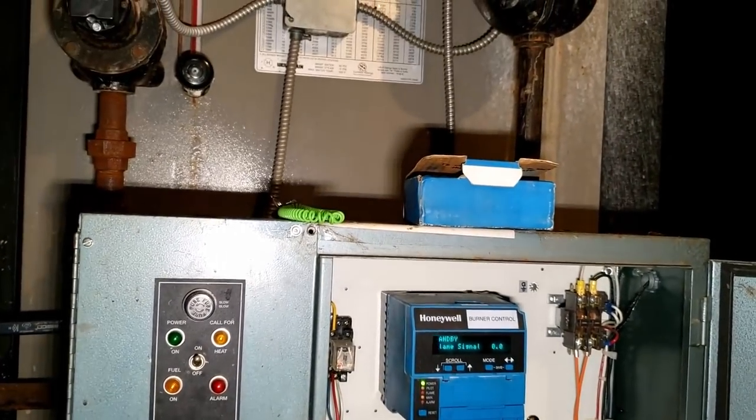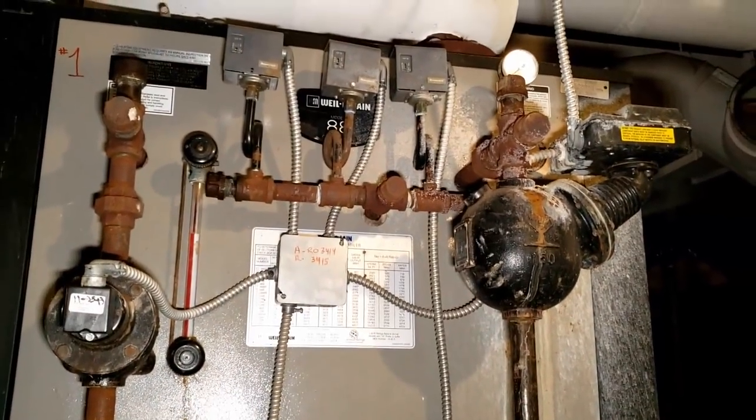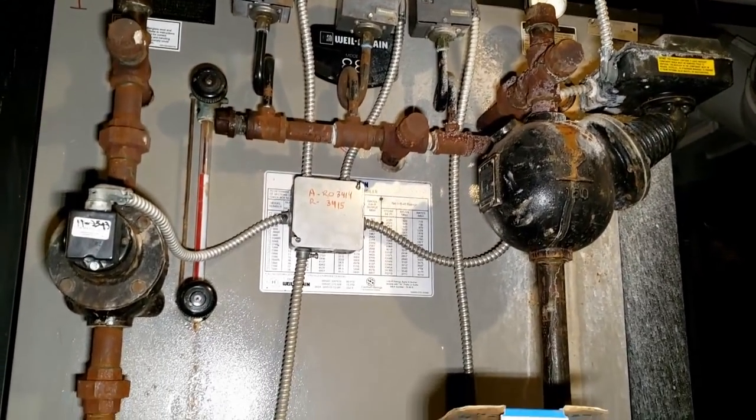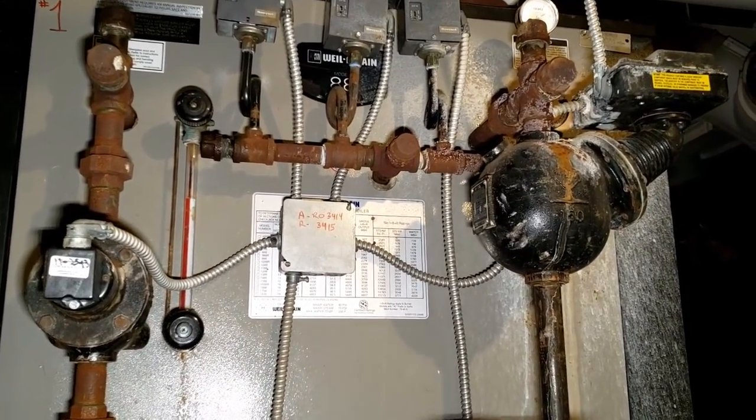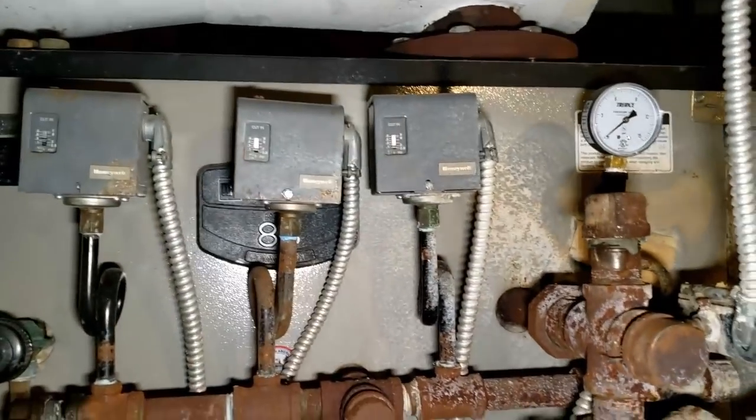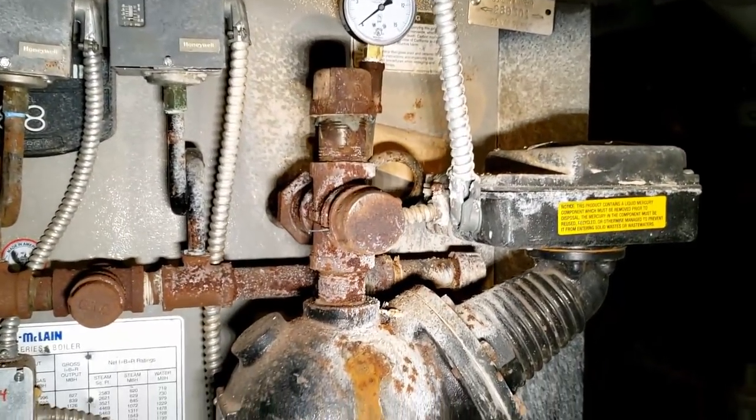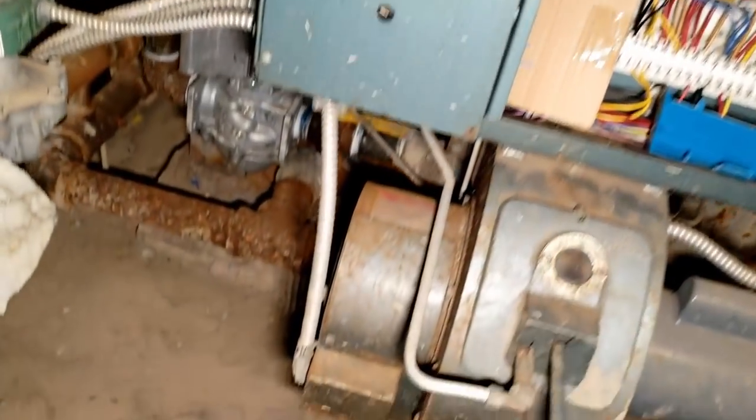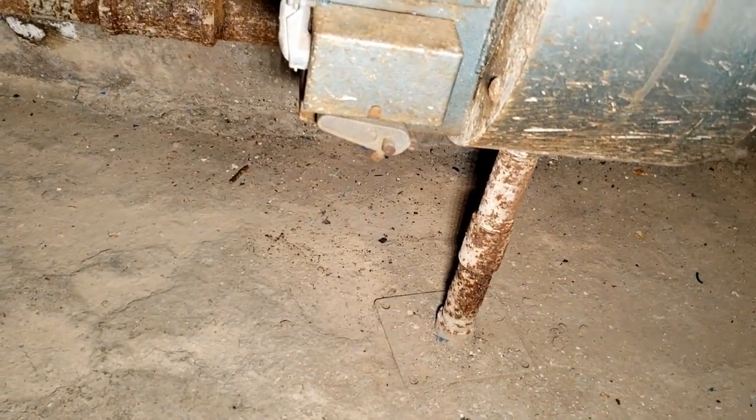Alright, so we've got a steam boiler here. This is one I've had to do quite a bit of work on. I just cleaned all the sight glasses up a few weeks ago, tested and cleaned all the safeties. Basically, it's not one to run. Had problems in the past with my end switch down here on the blower section, basically not closing, and that would keep it from getting its call to run.